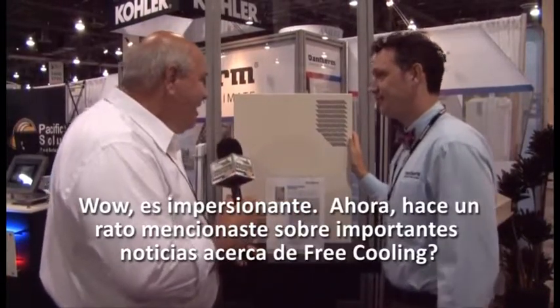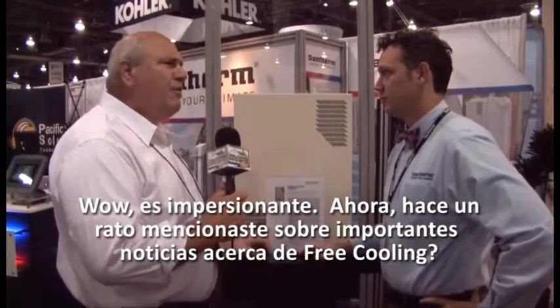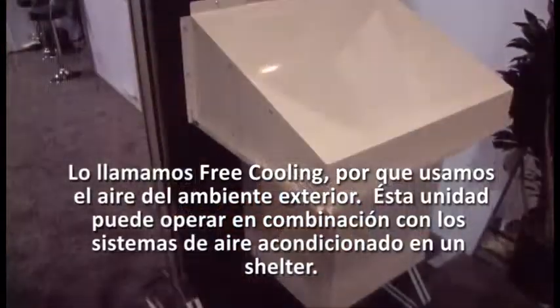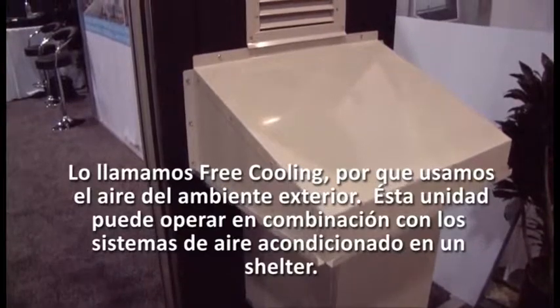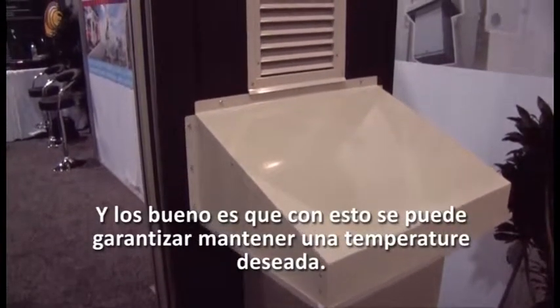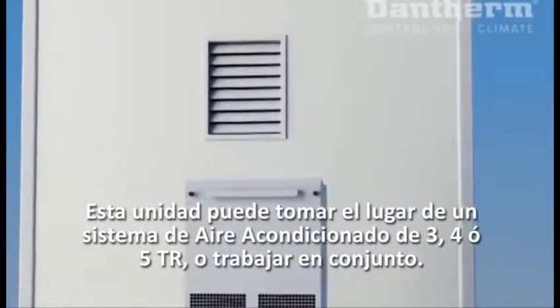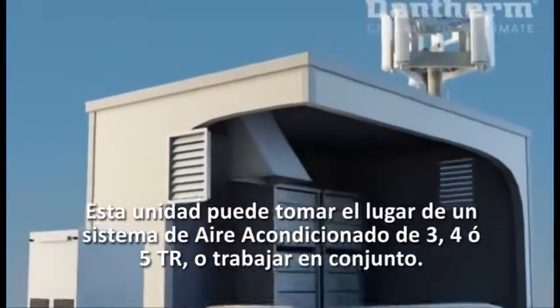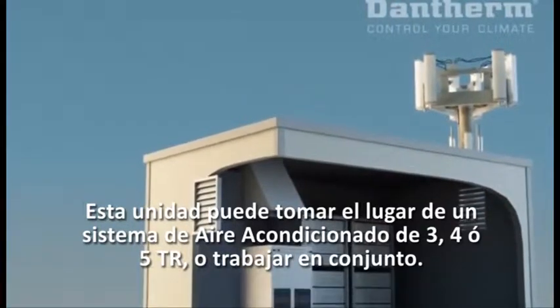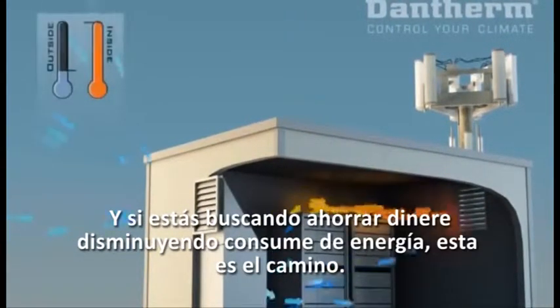Earlier you mentioned some exciting news about free cooling. We call it free cooling because we use the outside ambient air. This unit can be paired with an air conditioner on a shelter, and in temperatures that warrant good conditions, like Canada, the Nordic countries, or places in the US like New York, New Hampshire, and out west in Washington, this unit can take the place of a 3, 4, or 5 ton air conditioner, or be paired with one. If you're talking about saving money on your power bill, this is the way to do it.